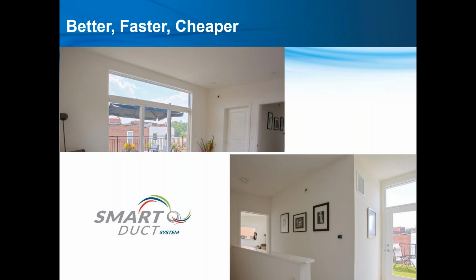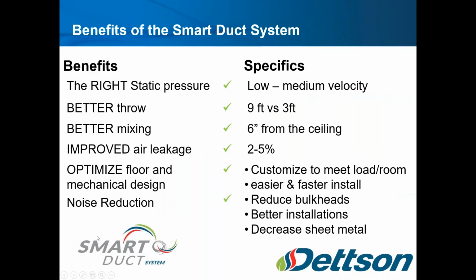And so now you've got all that usable floor space. You don't have registers on the floor anymore. You've got those diffusers 6 inches from the ceiling that are getting better throw, better mix, and a much more comfortable system. So just some benefits there of the smart duct system. We've got the right static pressure, low to medium velocity, better throw, 9 feet versus 3 feet, better mixing using that ceiling as a main plenum, better air leakage, 2 to 5% leakage, optimizing the floor plans, getting rid of expensive returns. Our system's efficient enough that you only need 1 return per floor.